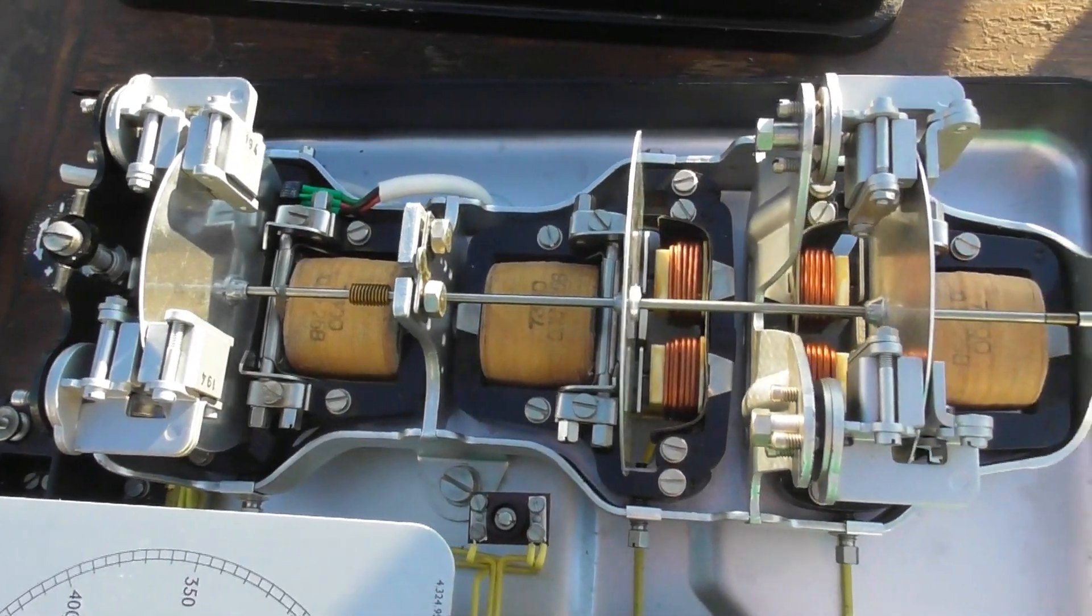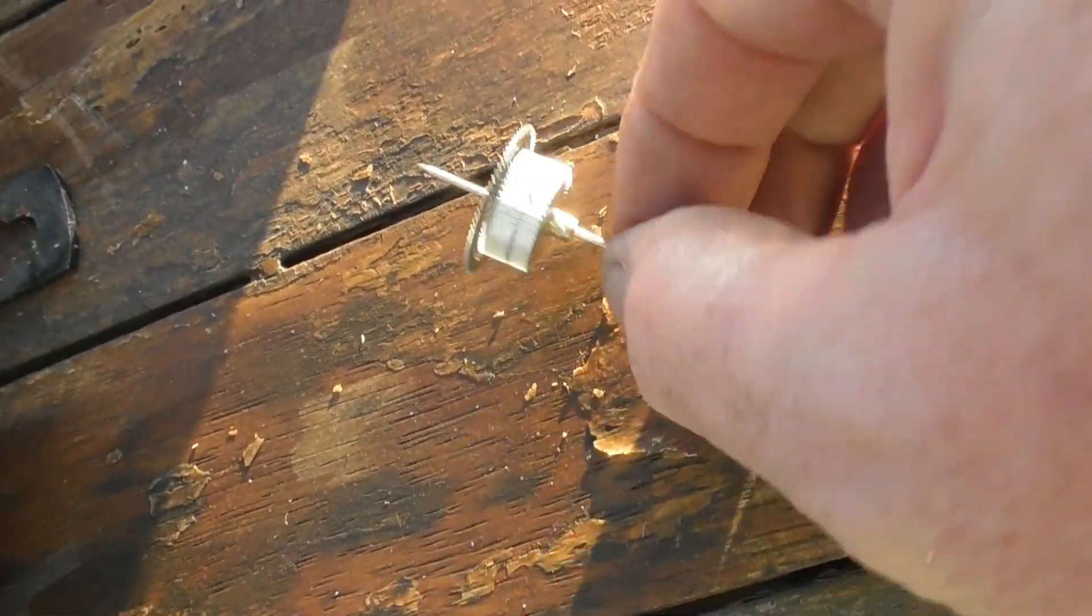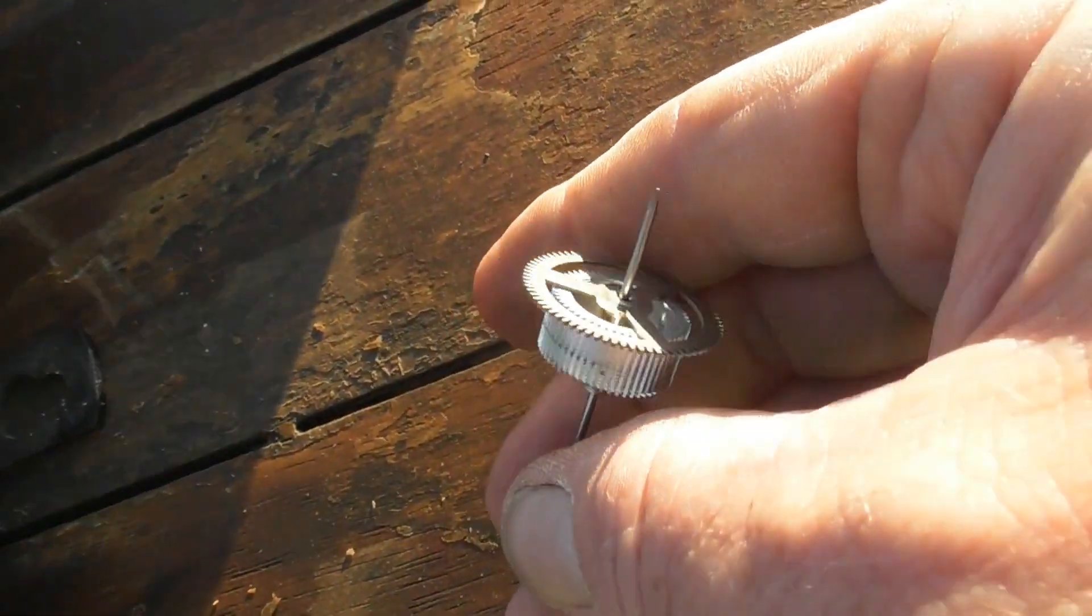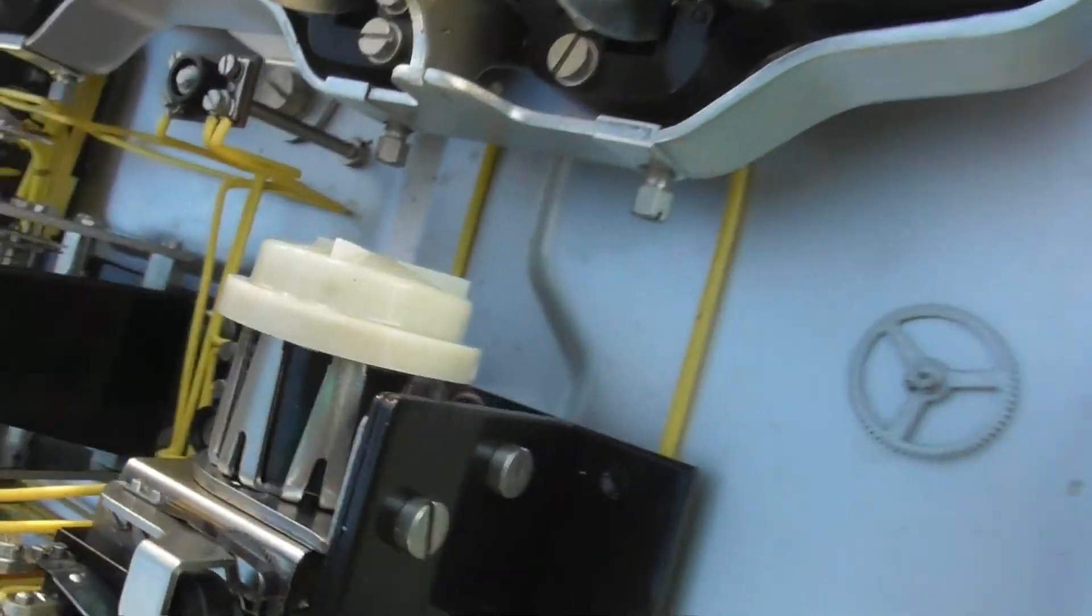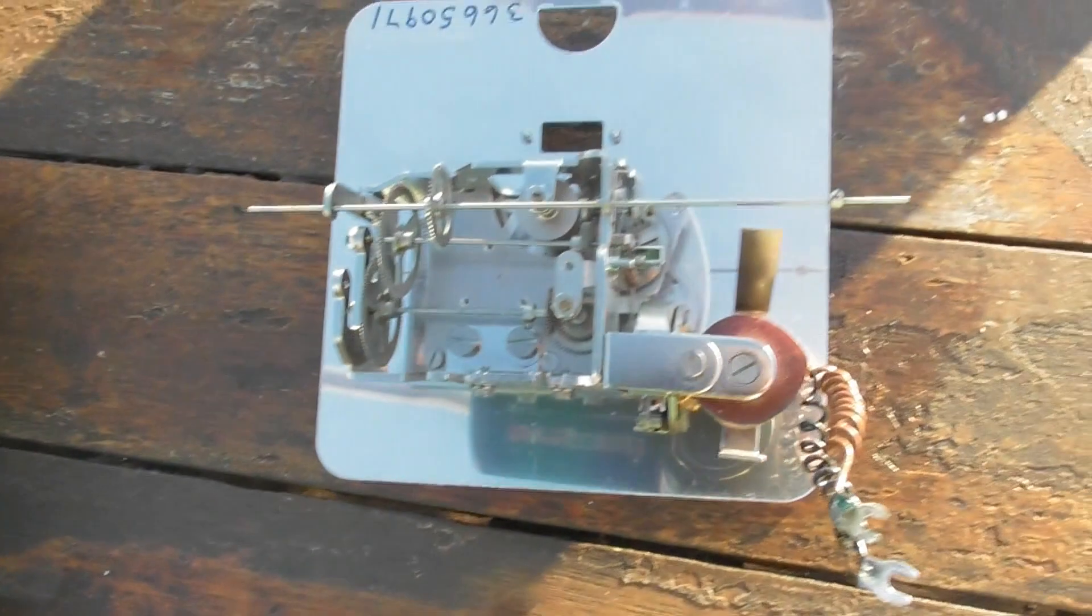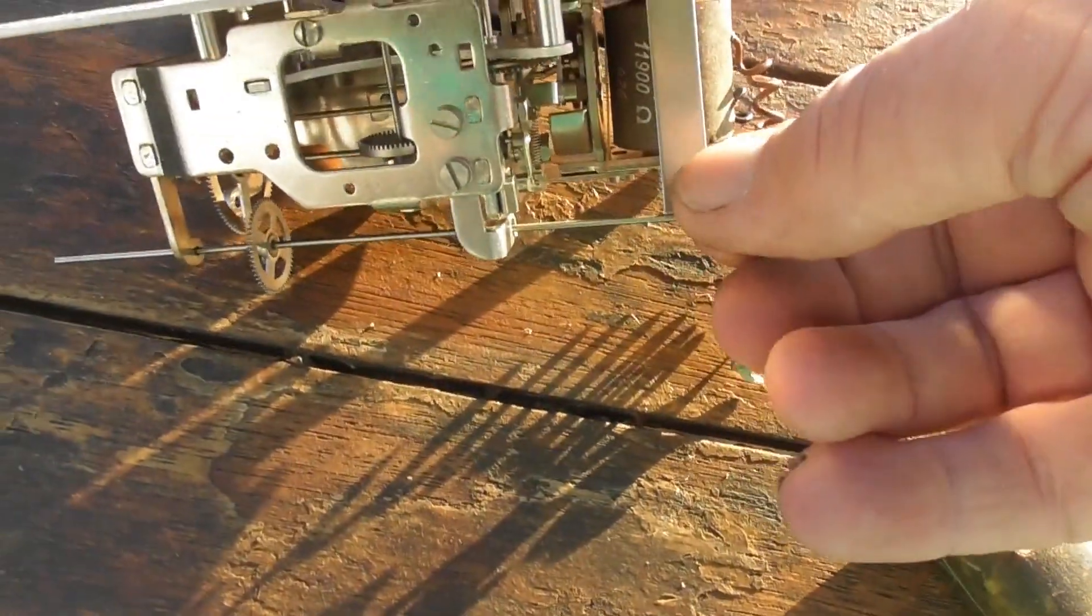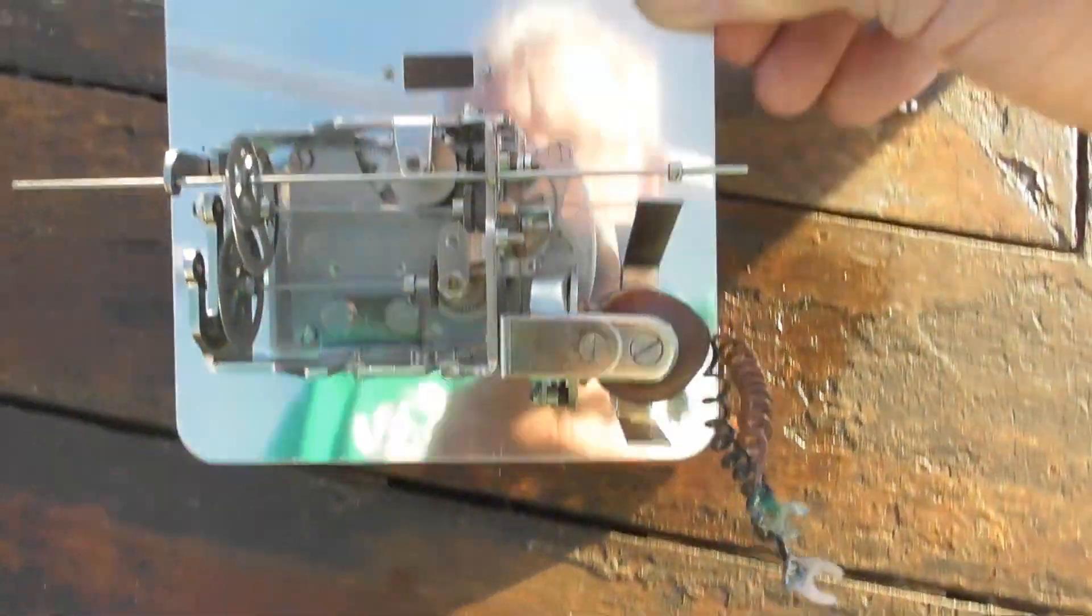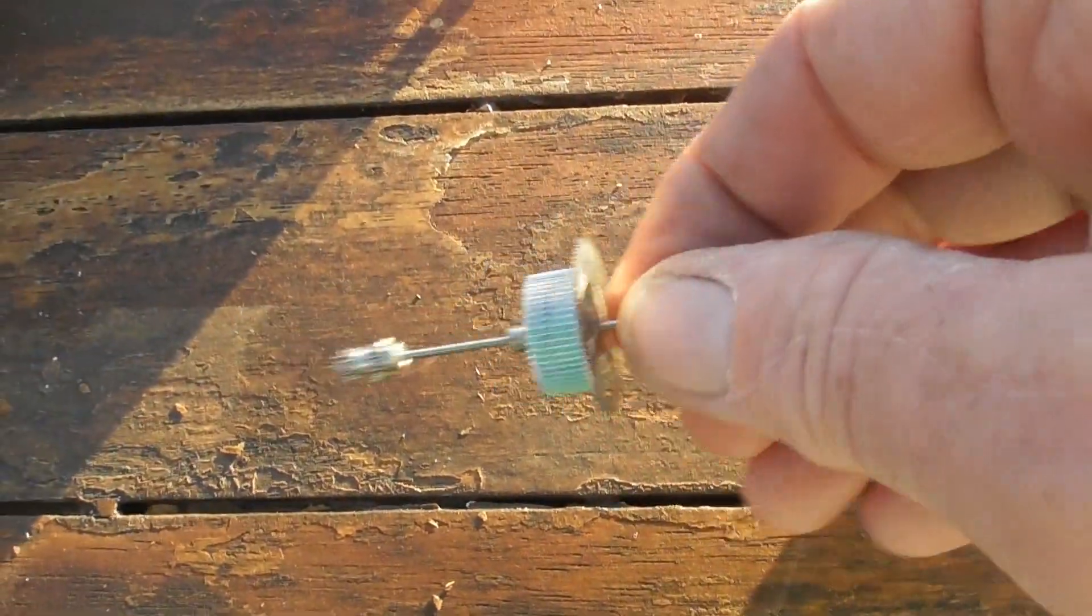I had to go a bit more in depth in this meter because it wasn't driving the kilowatt-hour register. I found this particular shaft has been bent - this is a drive shaft which drives the register here. Somebody must have had a play with this at one stage, but luckily I've got spare parts for these meters so I can fix this.